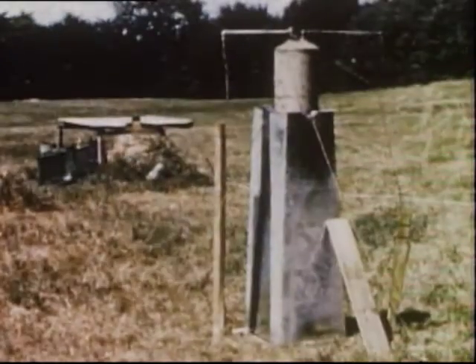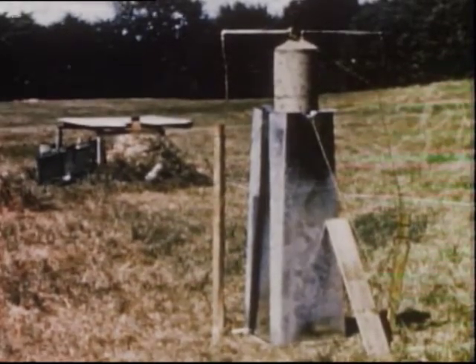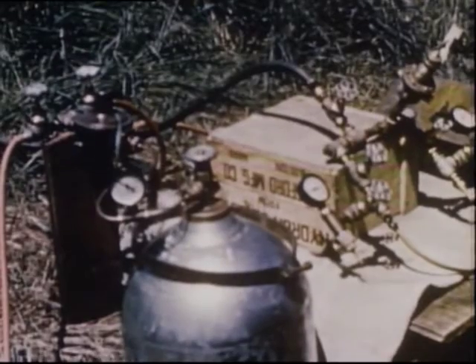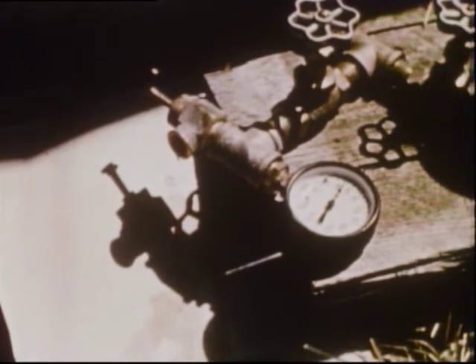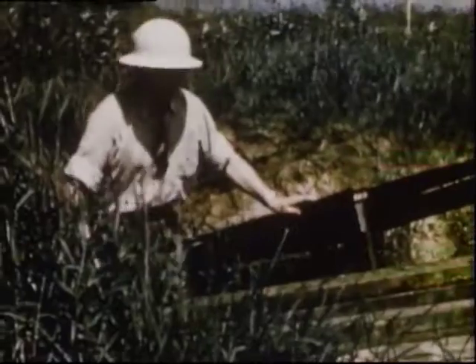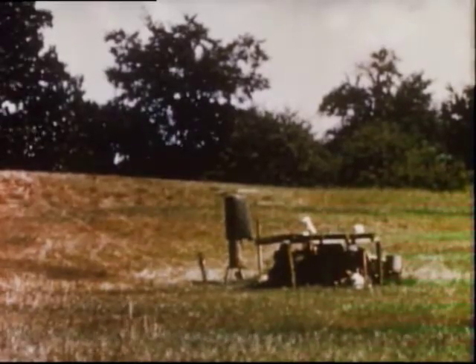It is obvious that temperature must be controlled to assure safety in hot water tanks. To continue this experiment in the field, a heavy duty tank is set up and heated by a gas heater. A pressure relief valve on the water supply line is dripping steadily at 75 pounds, taking care of the thermal expansion of the water, but the temperature continues to rise. When it reaches 302 degrees, cameramen spotted at strategic points are alerted for action.